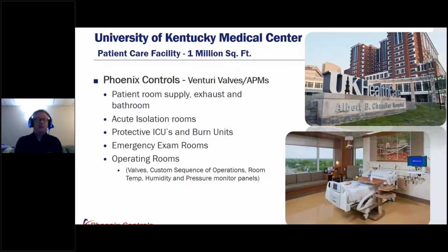The University of Kentucky Medical Center is sitting pretty good right now. They've had Phoenix Controls tracking pair, the systems we just talked about, in their patient rooms, both in the exhaust and in the bathrooms, the acute isolation rooms, ICUs, burn units, emergency exam rooms, operating rooms. All of those spaces are considered critical care spaces and need to maintain a good directional stable flow in order to maintain a healthy environmental quality, in order to reduce the inpatient risk, but also to maintain a flexibility for the hospital to accommodate situations like this, right? And so it does exist. They are out there, and we've had some good success with them.